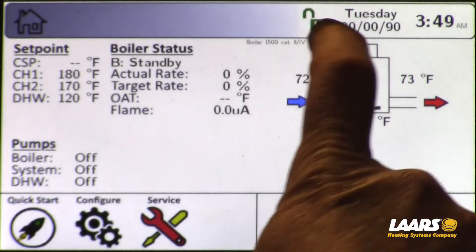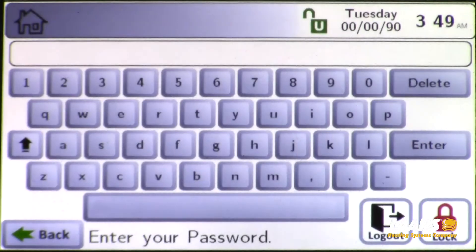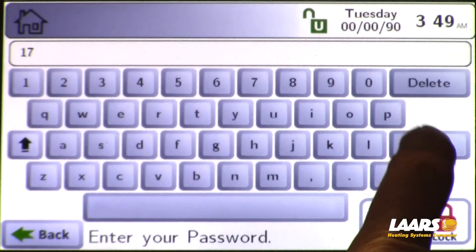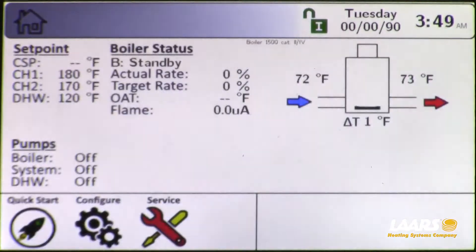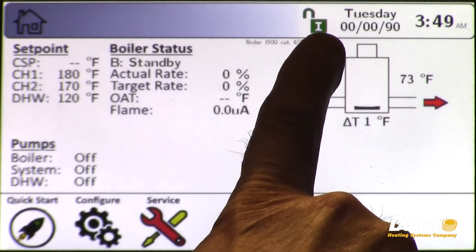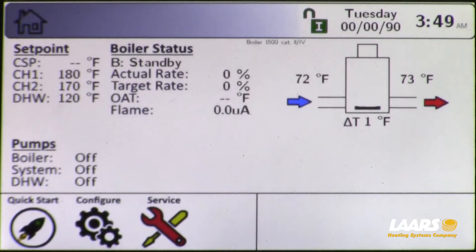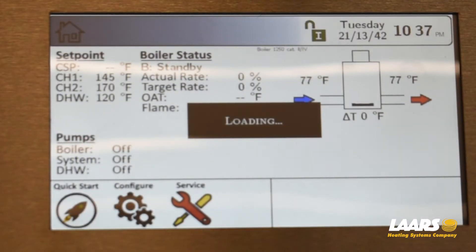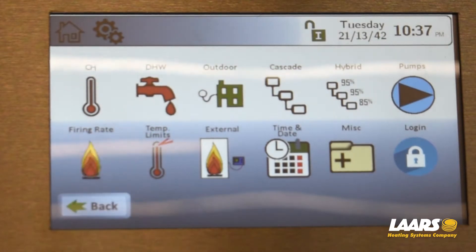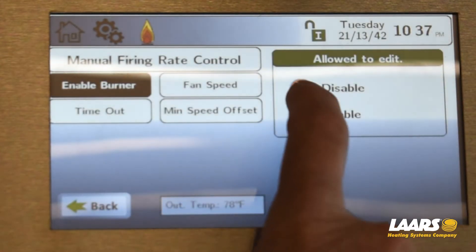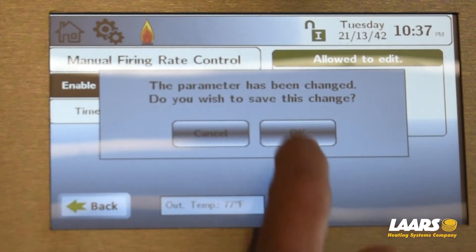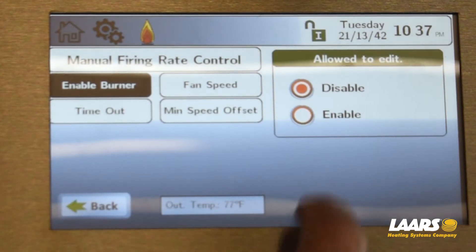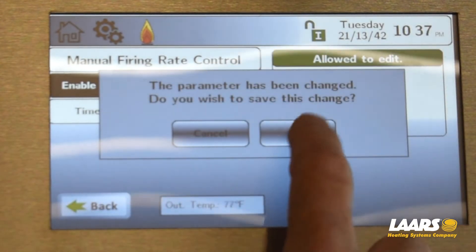We'll start by logging into the link display. From the home screen, click the padlock symbol, type in 1-7, and press enter. You'll see your padlock is now unlocked with the letter I for installer. Go to configure, then choose firing rate. It will be disabled when you get to firing rate control, so click enable and click OK.